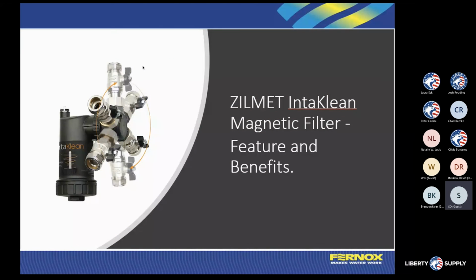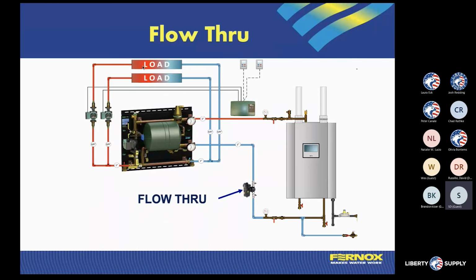Because these filters come in all different varieties, there's all kinds of different designs that we work with. One is the ability to change the fitting location. We need to keep the filter in a certain orientation based upon how we need to clean that system out. But we do have on most of our residential style filters the ability to adjust the position, or the smaller filters. So this would be 1 1/4 inch, a 1 inch, and a 3/4 style. You can adjust the position of the fittings.